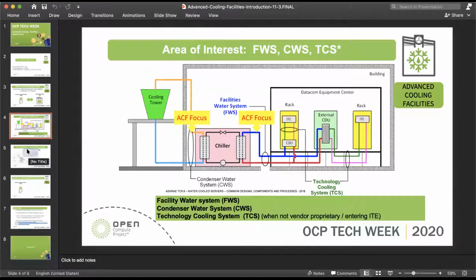which arguably can be successful with 45 degrees centigrade water, well above the temperatures generally required for chilled water and air-based solutions. And then the other question ends up being, would you even want to connect to the existing loop at all? Would you want to create a new loop, especially if your primary focus is going to be, say, cold plate or immersion cooling? Would it be more efficient or effective to put in an elevated temperature loop and not go through the issue of connecting to, say, a chilled water line?